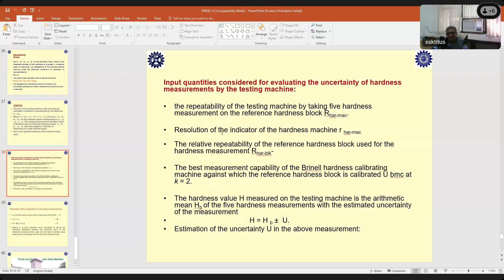And after the combined uncertainty, for a testing machine there will always be a difference, because your standard reference value and the average value that you are getting from the machine are going to be different. So that offset you have to account for separately when you are calibrating or checking the machine, and this error component has to be adjusted whenever you are making the measurement. Okay.